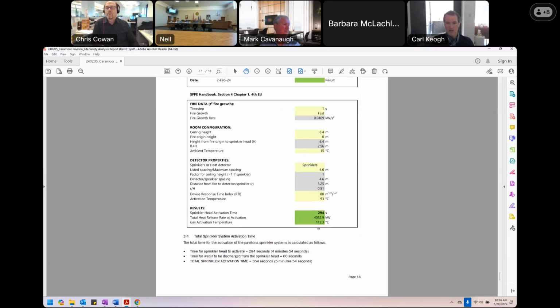So our sprinkler system would activate at 294 seconds, which is nearly 5 minutes, bearing in mind that it's an open environment and we have a relatively high ceiling within the structure. We add to that the fact that it's going to take another minute for the sprinkler system to fill with water. So water will discharge out of the heads just under 6 minutes from detection of a fire.